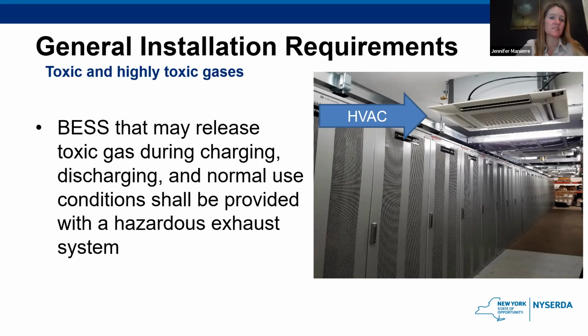Any energy storage systems that release toxic gases during charging, discharging, and normal use need to have some sort of hazardous exhaust system installed. Like I mentioned before, lithium ion batteries in particular do not release toxic gases during their normal operations of charging and discharging. So this is one of those areas of the code that will not end up applying to lithium ion batteries. But for many other battery types, it is a thing, and they need to have that exhaust ventilation.